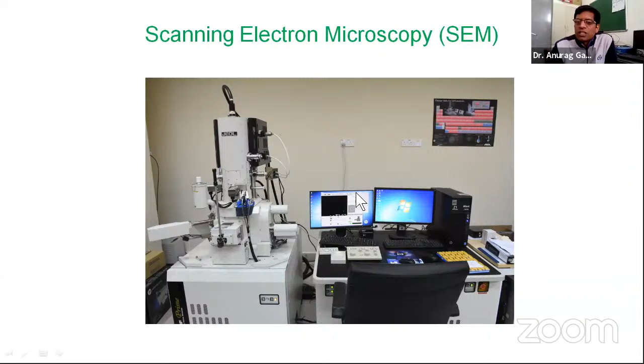If we compare the working, we have seen the light microscope, the transmission electron microscope, and this is the scanning electron microscope. The first you know already: light passes through and the image is projected over the screen. But in the SEM, the electron beam is focused and interacts with the sample at this place, and the backscattered and secondary electrons are detected by this detector, and after amplification they are sent to the CRT, the cathode ray tube, and here the image of your sample is formed. So this is the difference in the working principle of the SEM compared to the TEM.